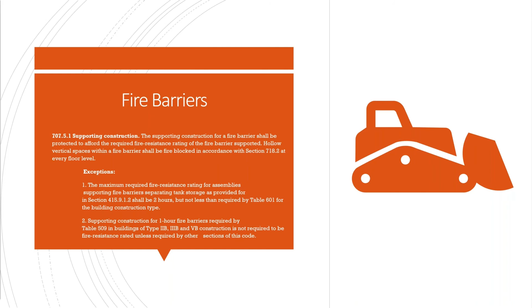And think about too, when you've got a fire barrier, we recently had a building where the construction type required a 1-hour floor assembly, but there was a use on the second floor that required a 2-hour fire barrier separation. And during construction, it was found that this 2-hour separation on the second floor wasn't supported with 2-hour supporting construction underneath, because the building element for that construction type only required that floor to be 1 hour. So make sure to look at all the pieces. If you've got a 2-hour fire barrier on a floor that's only required to be 1 hour, that floor is not rated the same as that wall, and that supporting construction needs that same rating. So anyhow, this section talks about that, and there are some exceptions to that for different construction types.